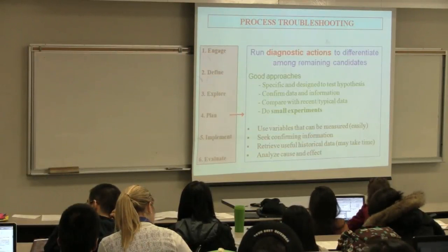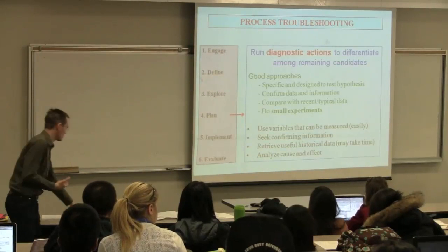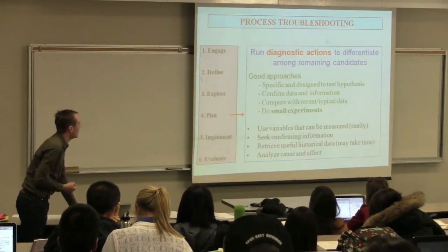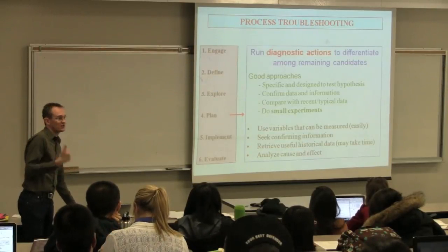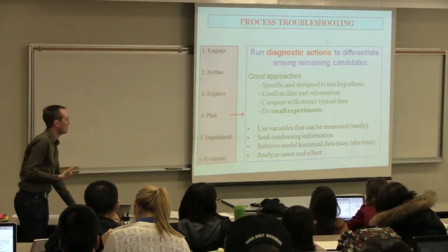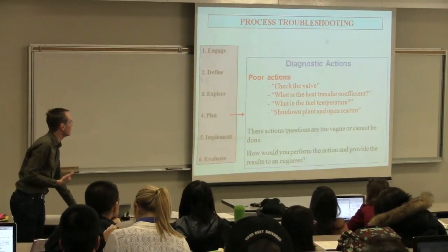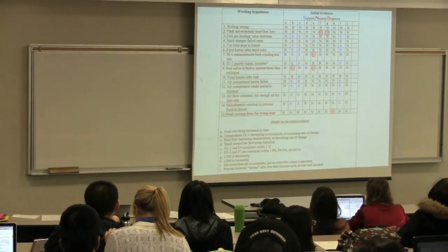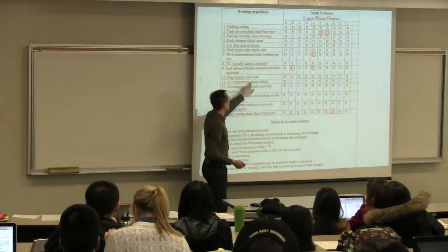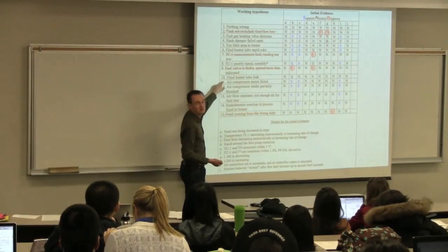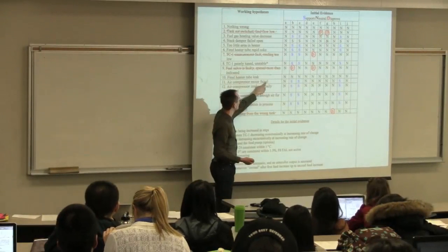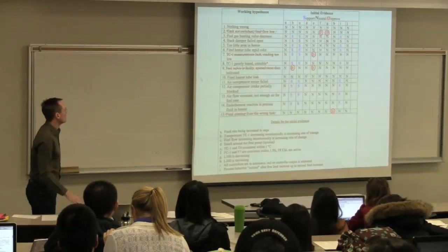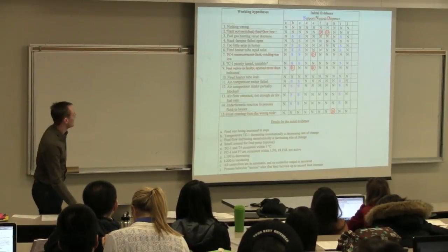If your safety and interlock systems have been initiated, then there's a good chance that a lot of those further steps you're just not going to require. The process is about to be shut down. Or alarms. It's not just SIS, but also the alarms. If alarms are going, then it can quickly eliminate some of those hypotheses. For example, if the safety and interlock system was initiated, you can be sure that the air compressor motor failing is not a valid hypothesis. The SIS system will not go off if the air compressor has failed. So then you can eliminate that from consideration.